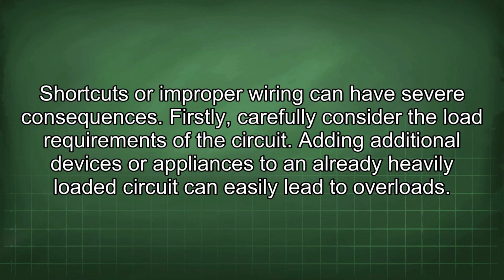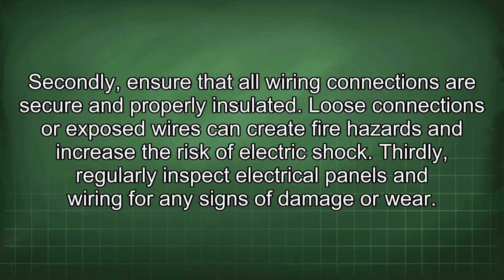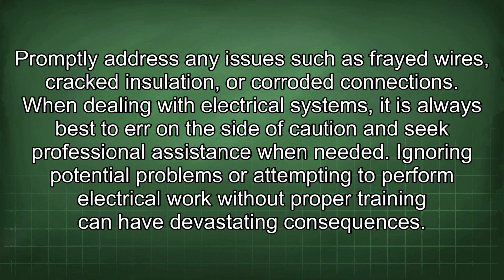Shortcuts or improper wiring can have severe consequences. Firstly, carefully consider the load requirements of the circuit. Adding additional devices or appliances to an already heavily loaded circuit can easily lead to overloads. Secondly, ensure that all wiring connections are secure and properly insulated. Loose connections or exposed wires can create fire hazards and increase the risk of electric shock. Thirdly, regularly inspect electrical panels and wiring for any signs of damage or wear. Promptly address any issues such as frayed wires, cracked insulation, or corroded connections.